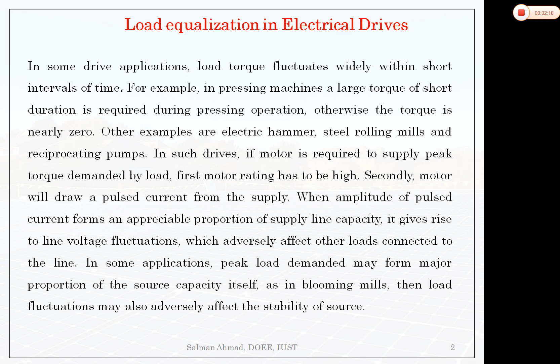So there will be two problems. One is, if the motor has to supply such a high torque, then the rating of the motor will be high. The second problem is, it will draw a pulsed current from the main supply, which will affect the other loads connected with the same main supply. So for this reason we have to adopt a load equalization method, so that the motor rating is small and the current drawn from the main supply is not in pulsed form.